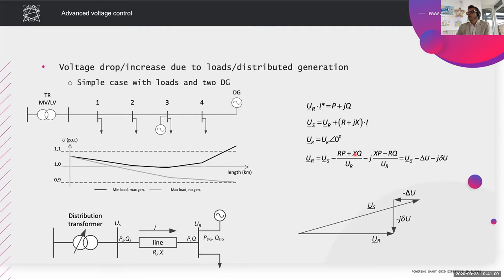And you can see, if you forget about the reactive power and focus only on the active power, you have one here and one here. If the active power is positive, so we usually use positive for loads, then the voltage on the consumer side will be lower than the voltage on the network side. So clearly we have a voltage drop on the line.